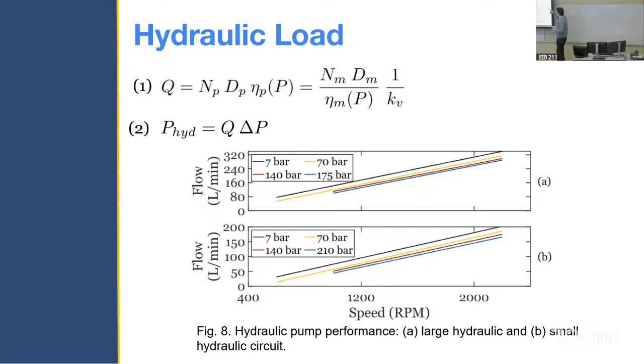You can think, well, if you're operating at a higher pressure, you're going to see more leakage through your pipes, so you're not going to displace quite as much fluid to the motor. So that's what that volumetric efficiency is we're taking into account.